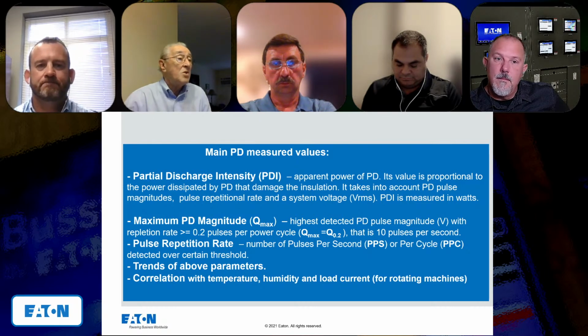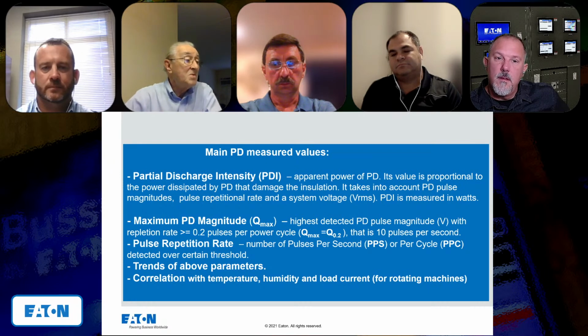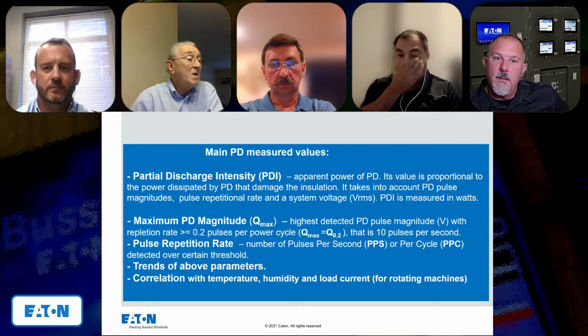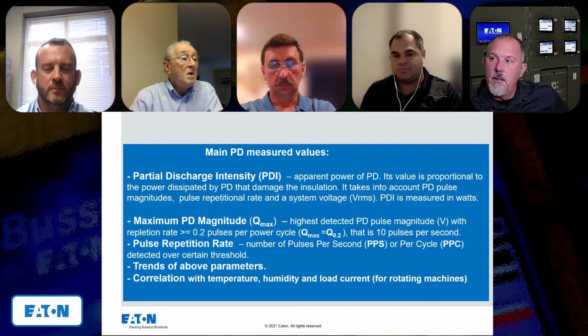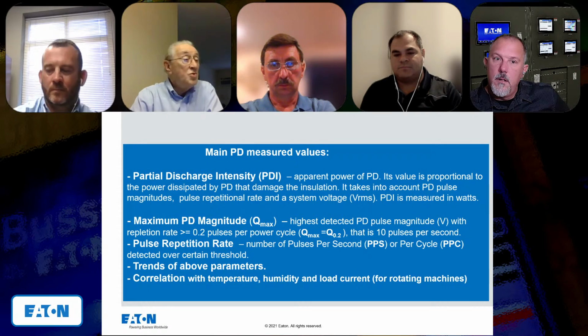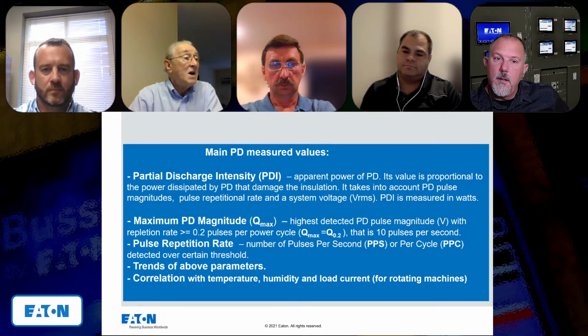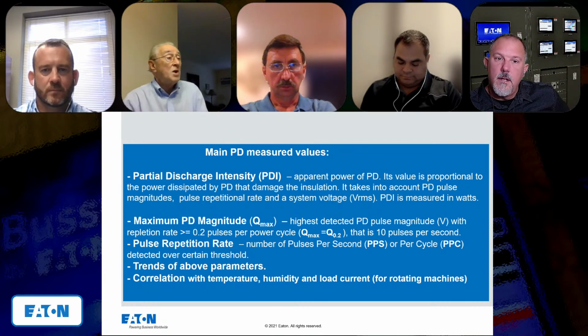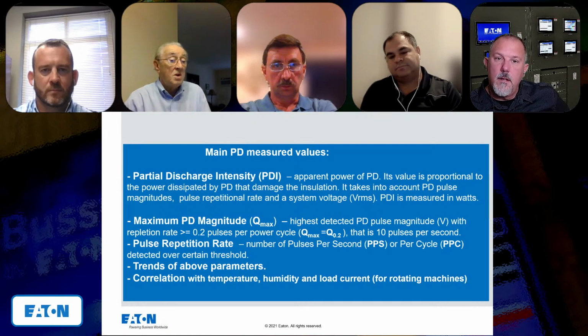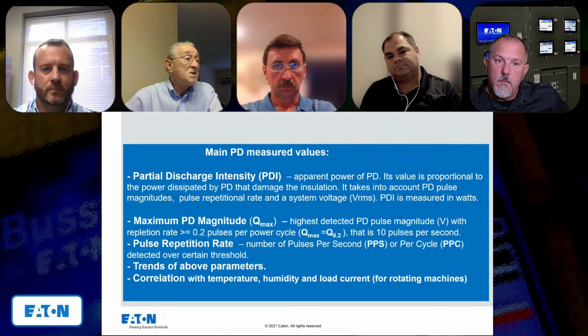One can have a lower level but not stable, and it will increase with time. So the trend is sometimes a very important parameter, especially because there is no threshold for all equipment. You don't know what partial discharge intensity or power is acceptable or not acceptable. There is no definite threshold.